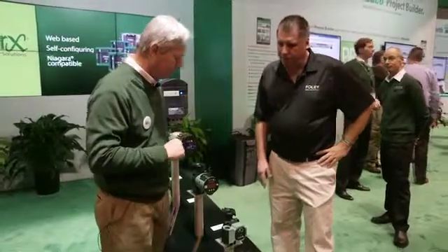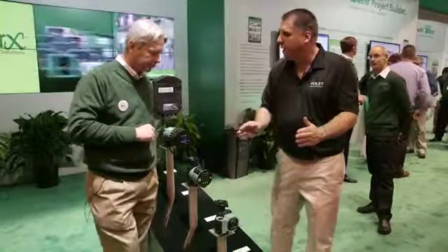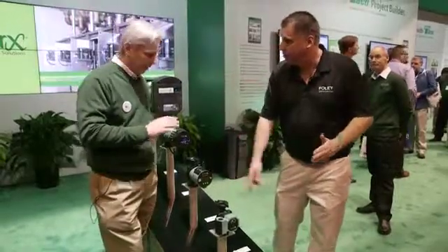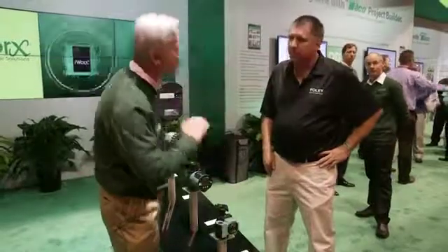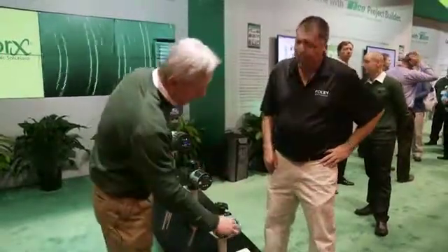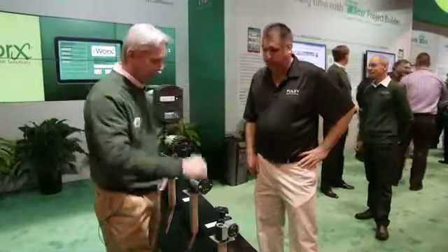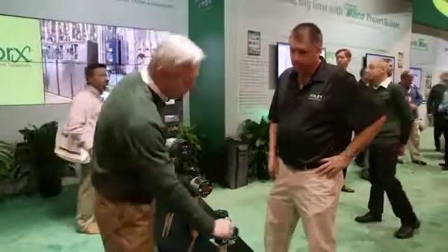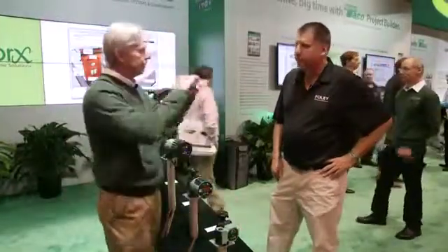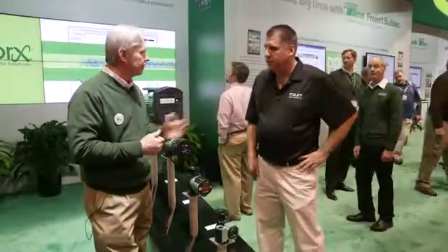Doug, let's say I had a residential project using this pump and maybe 3 or 4 Sentry zone valves. Is that a good application for this pump? It could be a good application. What we recommend in that application is setting it on constant pressure. It has 3 settings, so 5, 10, or 15 feet constant pressure. For example, for the 007, which everyone's familiar with, you might want to set that to a 10 feet shutoff head. So it'd be a great application for zone valves, Zone Sentry applications.